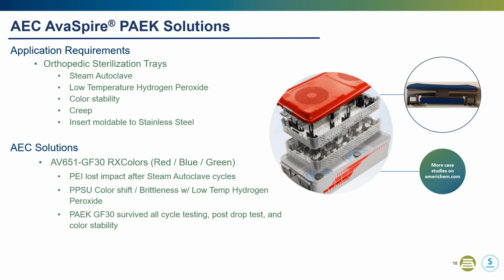Some industries call 30% glass-filled nylon space-age plastics. I like to reserve that for PEEK personally. PEEK is for demanding applications, with high loads, high heat resistance, and fatigue strength. Here we have a metal to plastic conversion for an articulating arm on a surgical robot. The OEM wanted the material to have long-term high strength, the ability to have metal inserts, metal bearings, so the material had to be overmoldable, and they had mating parts, so they wanted the material to be like.